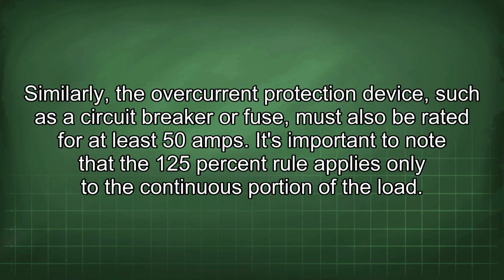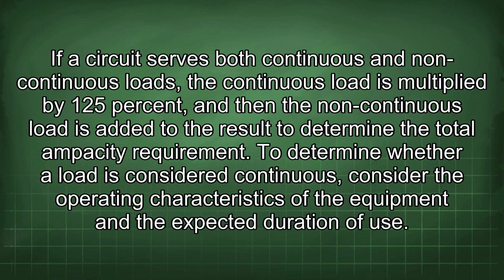Similarly, the overcurrent protection device, such as a circuit breaker or fuse, must also be rated for at least 50 amps. It's important to note that the 125% rule applies only to the continuous portion of the load. If a circuit serves both continuous and non-continuous loads, the continuous load is multiplied by 125%, and then the non-continuous load is added to the result to determine the total ampacity requirement.